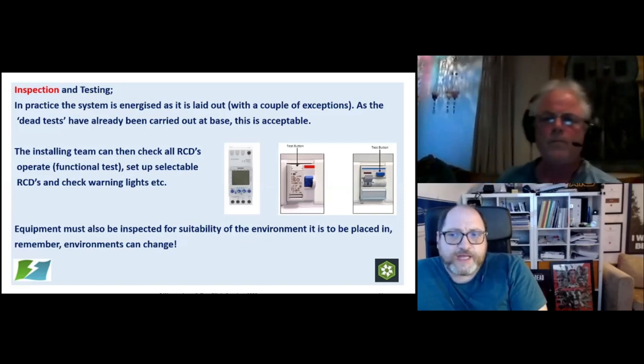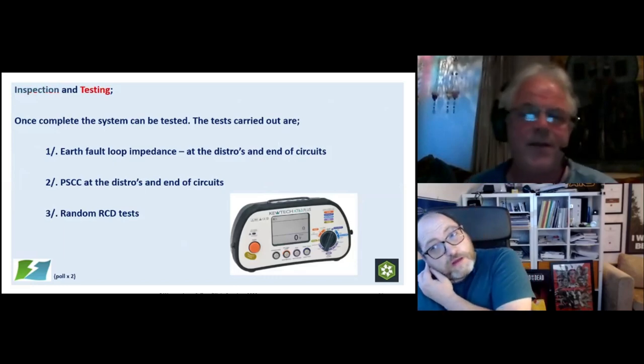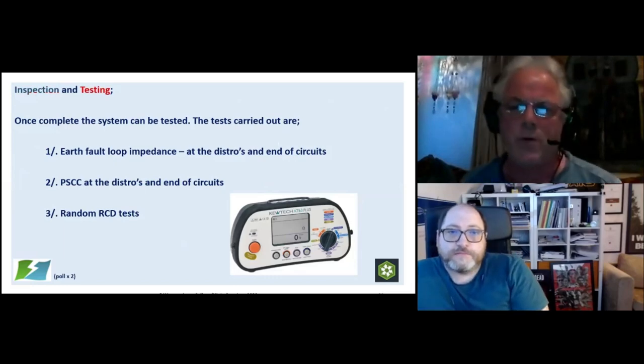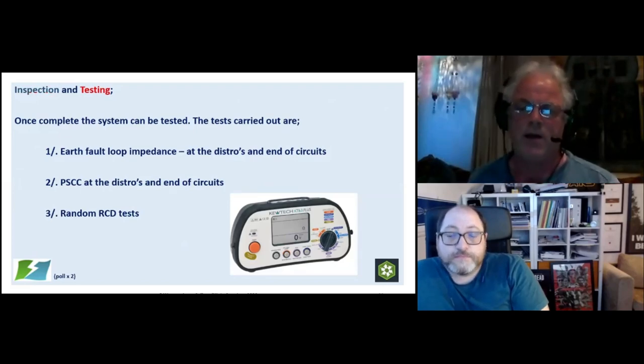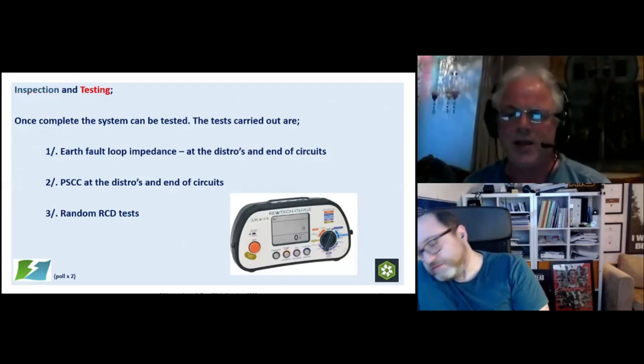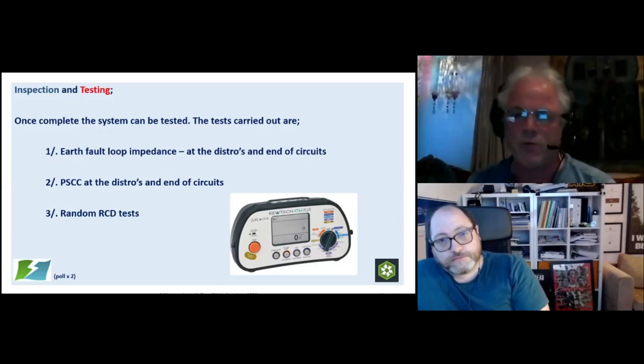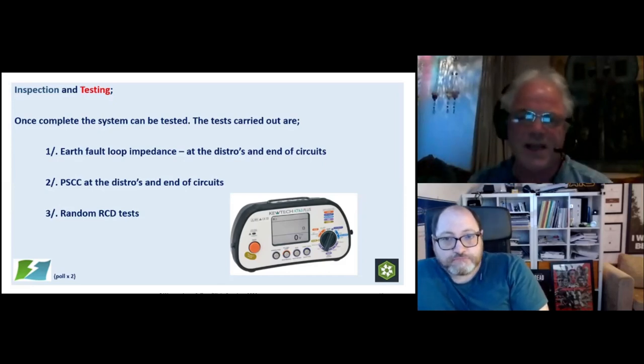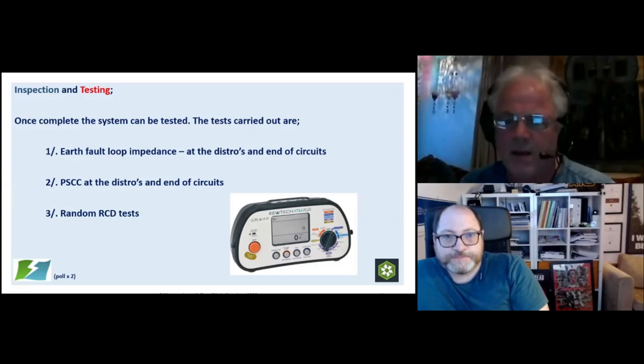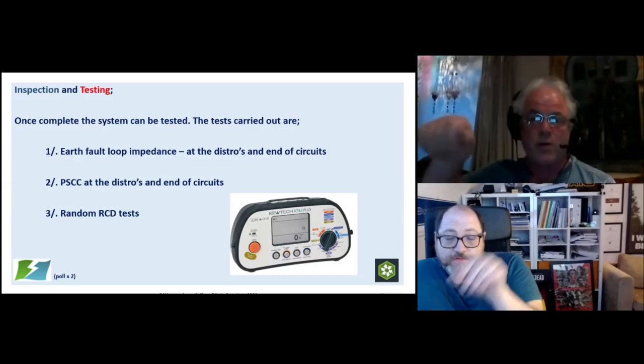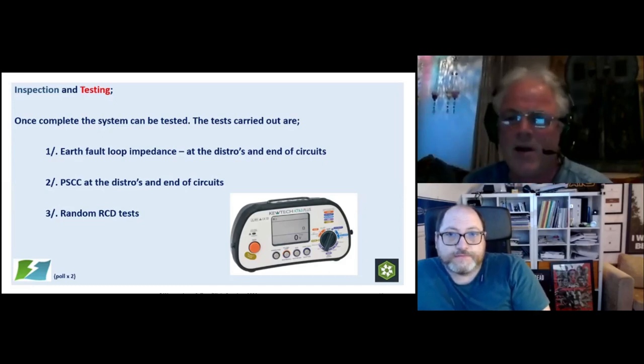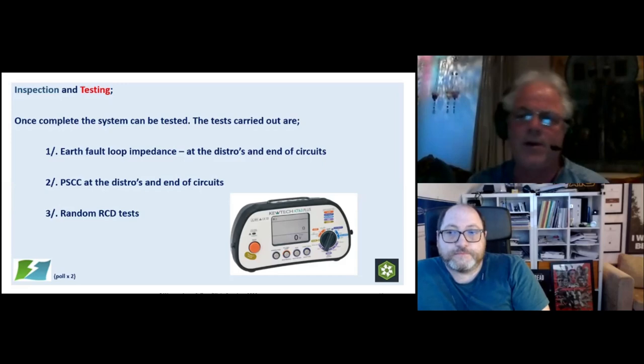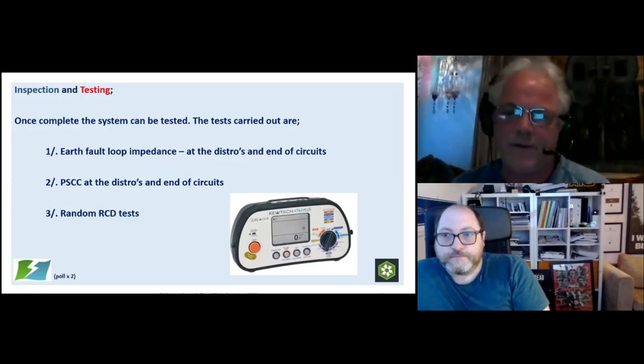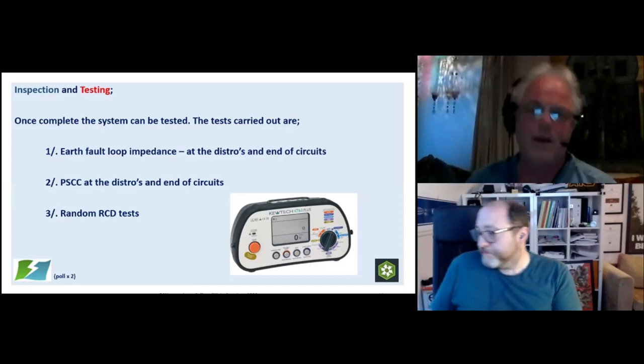It does take a bit of testing, though, to get it balanced right. And the thing is that if you've got one of these newer type digital RCDs where you have to push buttons in a certain order, with different makes and different models you have to set up in different ways. If you haven't got the instructions, it's a blooming nightmare. The older type ones where you had the screw terminals and dials, fantastic, you can see what you're doing. But having set them up, I would always test them, because you may be looking at it thinking, well, that's on 300 milliamp. When you actually test it, it might actually be 350 milliamp or 360. That's one great benefit of the ramp test now as well. Yeah, ramp testing is ideal.